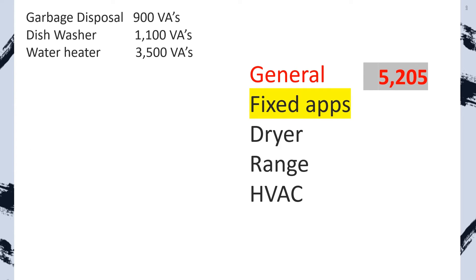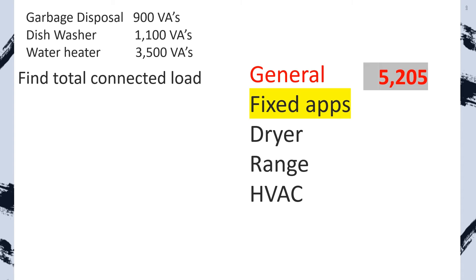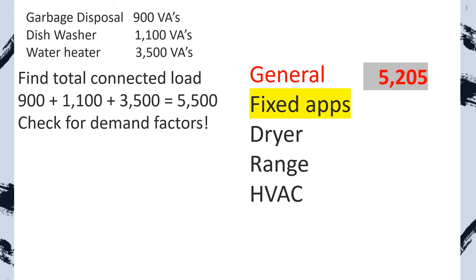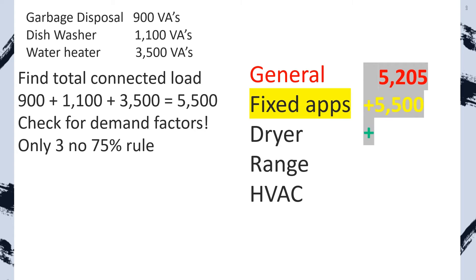Now let's do our fixed appliances. We have a garbage disposal, dishwasher, and water heater. Find the total connected load — we total them all up and it equals 5,500. Now we check for demand factors. There are only three appliances, so the 4-or-more 75% rule does not apply, and we write down 5,500.